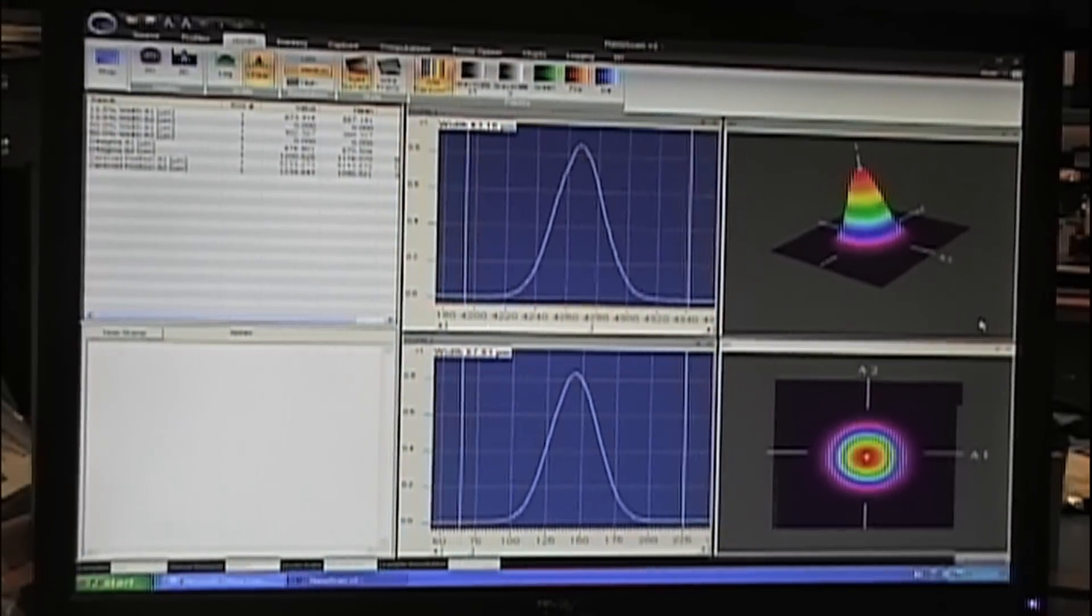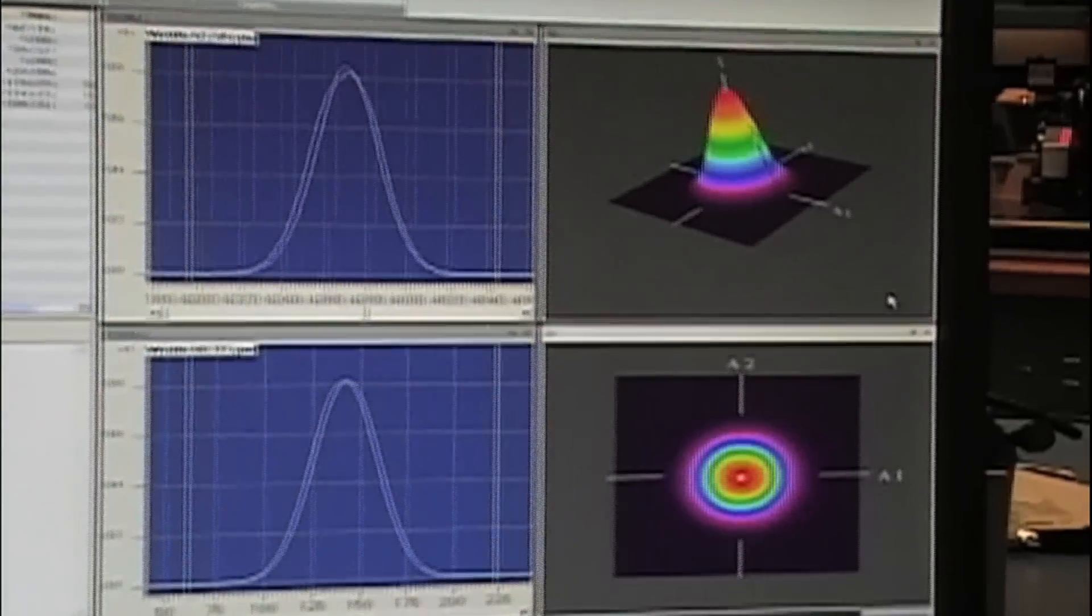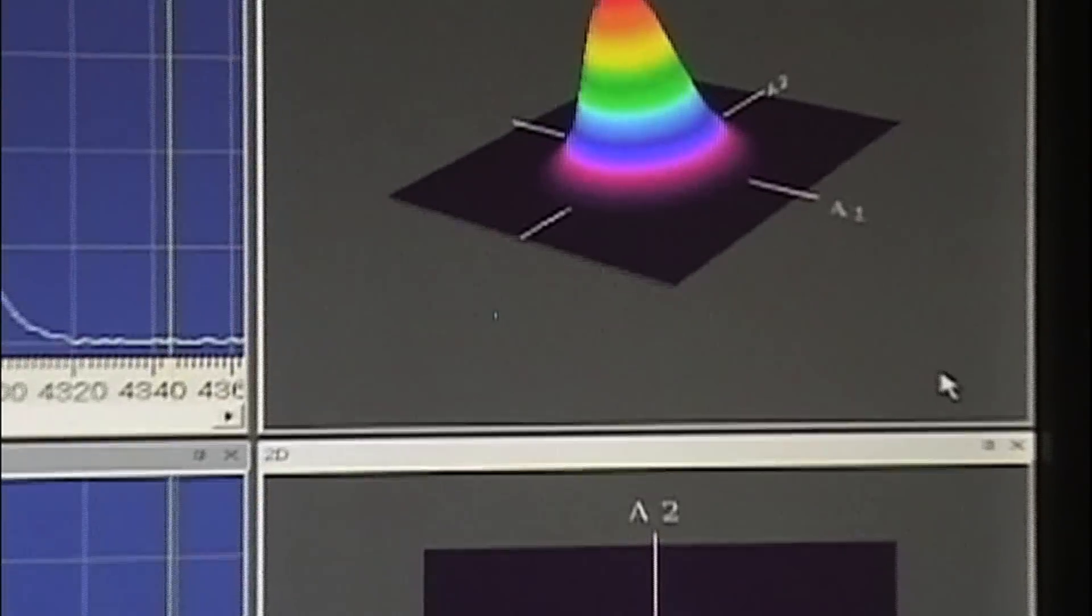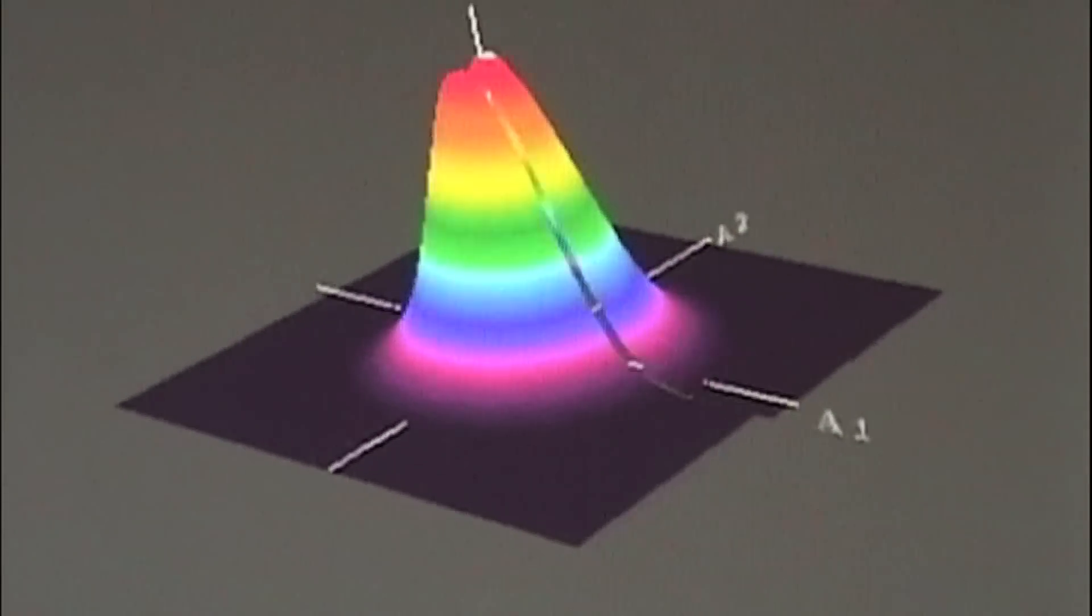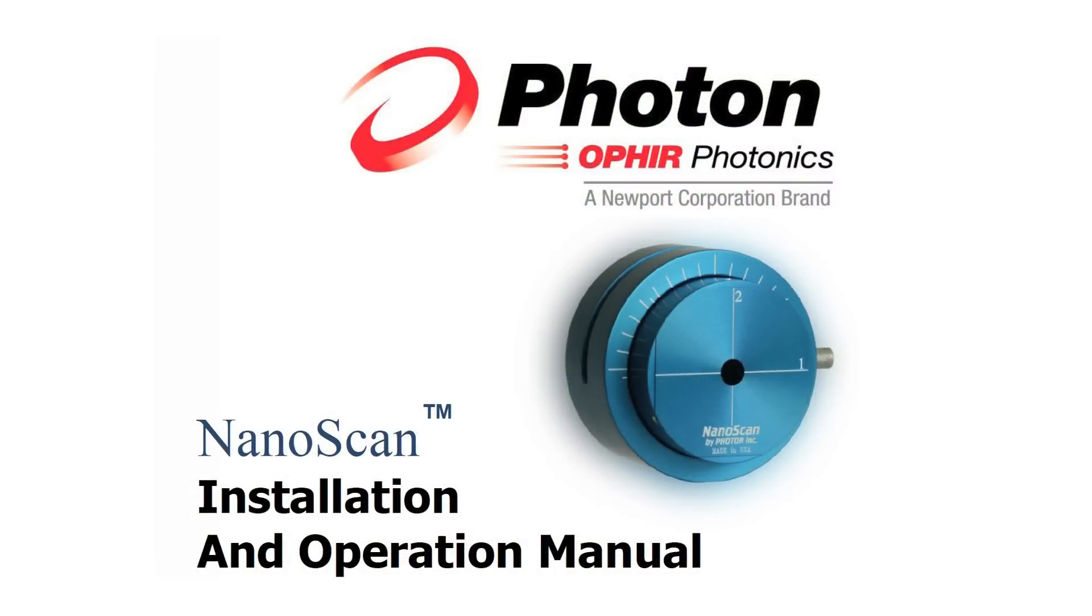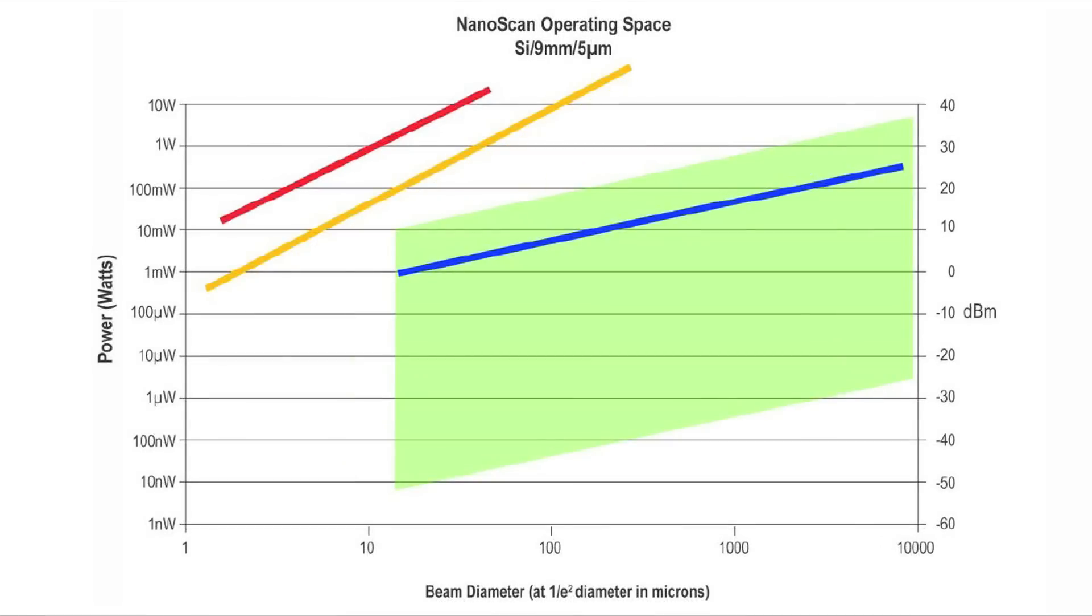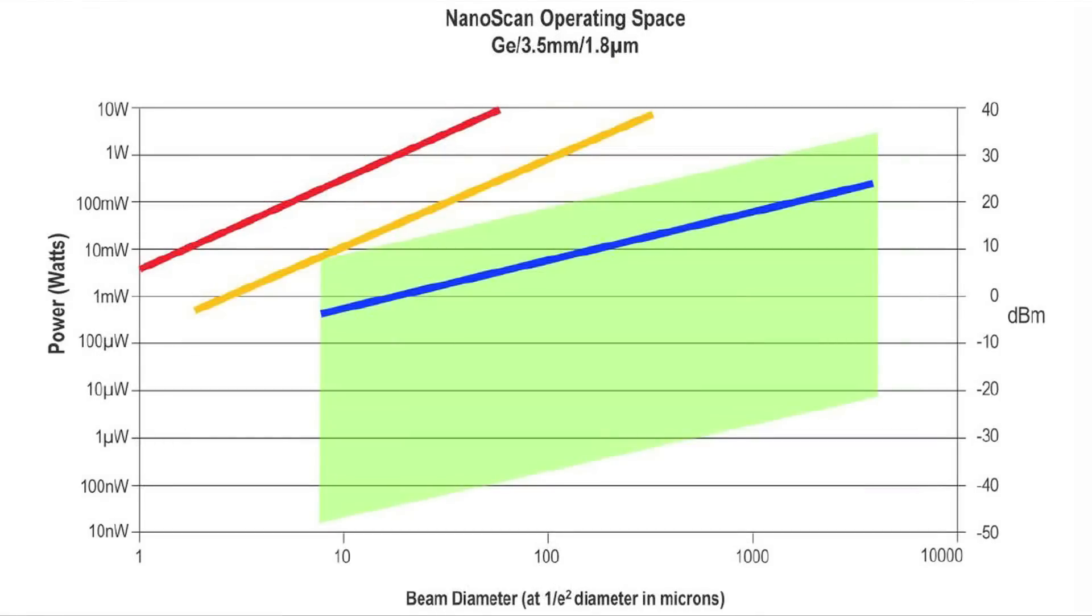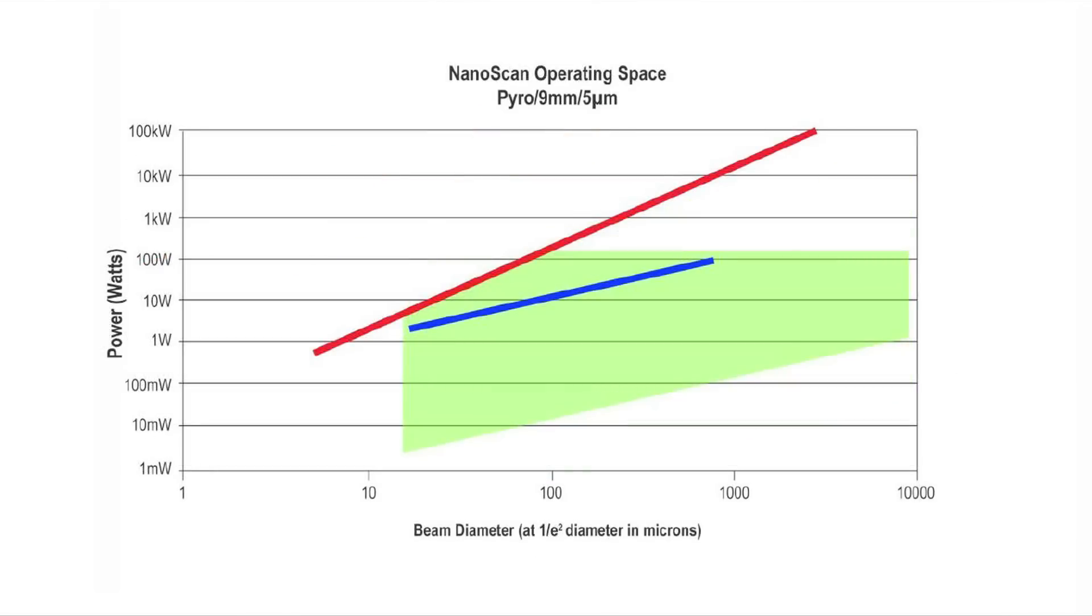The nanoscan measures the beam width very accurately, but some knowledge of the input beam width and power is required in order to safely set up the nanoscan for beam width measurement. The nanoscan installation and operation manual includes operating space charts for all nanoscan types. These charts indicate the power and beam size ranges for safe operation.